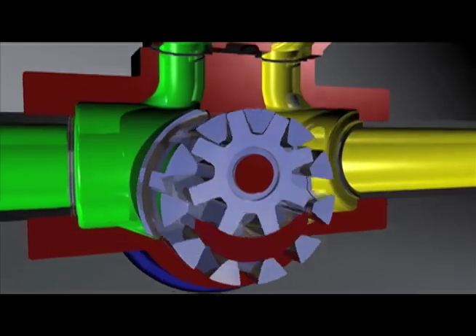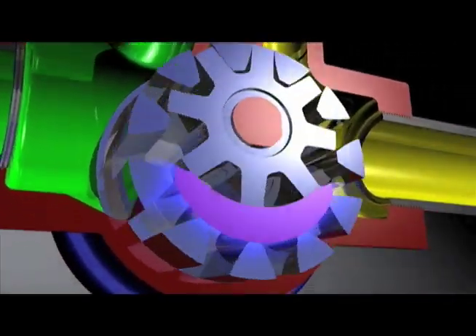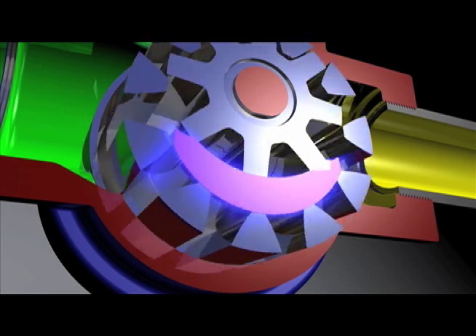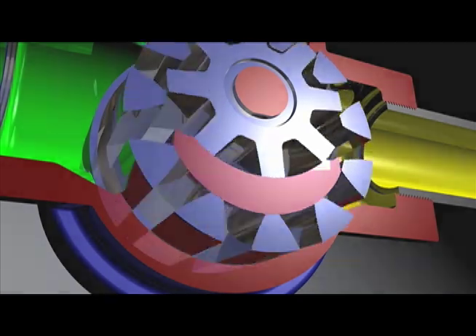As the rotor and idler rotate, the fluid is prevented from returning to the suction side by the crescent located on the head of the pump, which seals the area where the teeth are out of mesh.